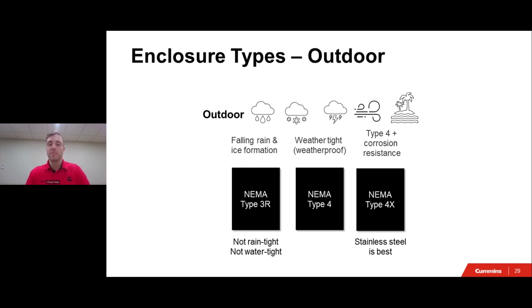So these are still NEMA type enclosures. However, they provide a little bit more protection. So for starters, there is the NEMA 3R, which is off to the far left there on this slide. This enclosure is intended for outdoor use. The 3R enclosures provide a degree of protection against falling rain and ice formation. These are constructed with knockouts on the sides and bottom of the case to prevent beating rain from interfering with successful operation of the apparatus or resulting in wetting of live parts and wiring within the enclosure under specified conditions.